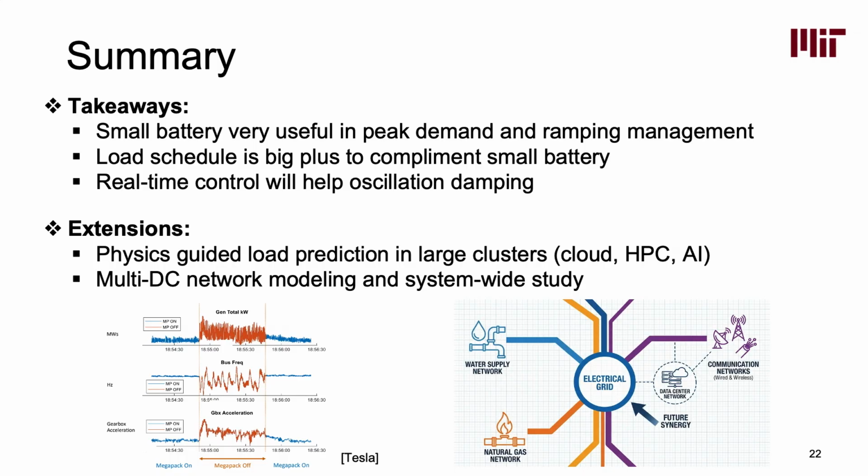And lastly, there's a very interesting example I got from a talk last year by Tesla people, when they were building the xAI hyperscale data centers. They tested using on-site generation, because what they requested was a 500 megawatt capacity, but the utilities only offered roughly 200 megawatts, if I remember correctly. So for the additional generation, they bring their own on-site gas turbines, which is the blue curve here.